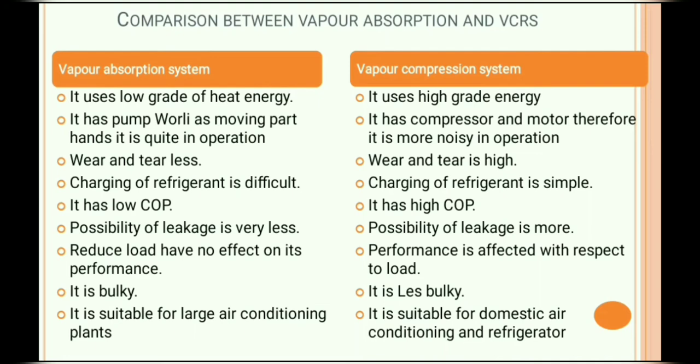The second difference is what? In the vapor compression system, the compressor and motor are the moving parts, and therefore it is more noisy in operation. But if we talk about the absorption system, the pump is the only moving part, therefore it is quiet in operation. That means VCRS is noisy in operation and the vapor absorption system is quiet in operation.